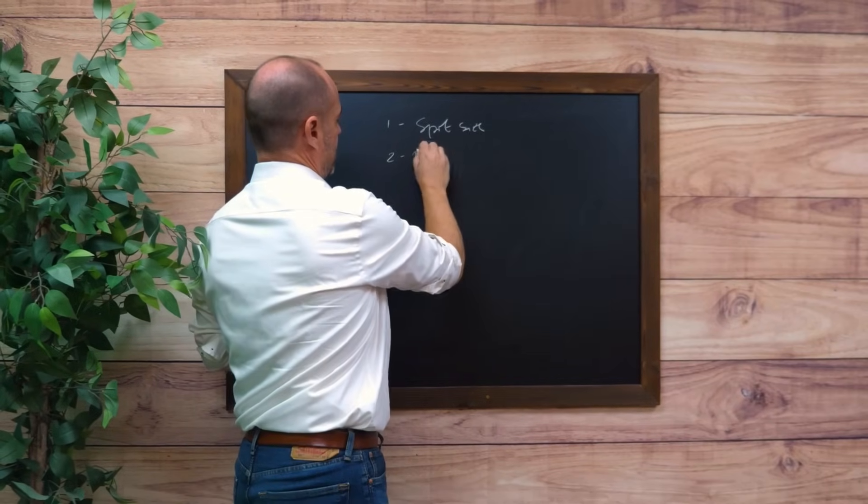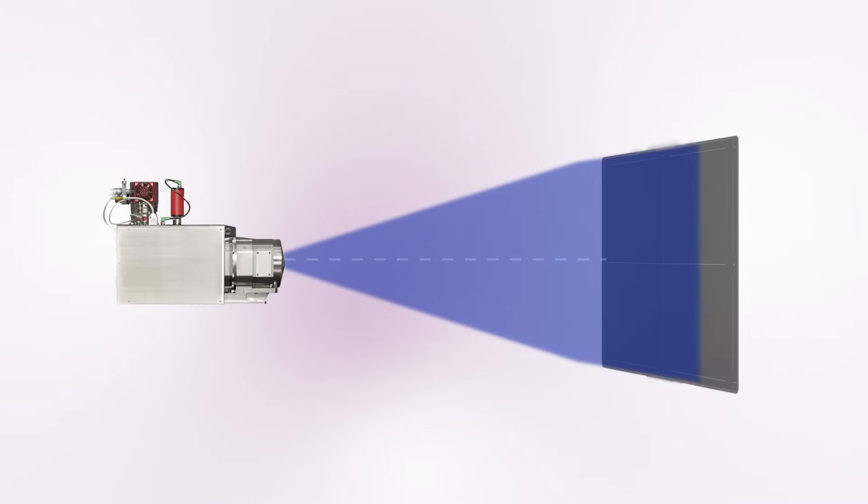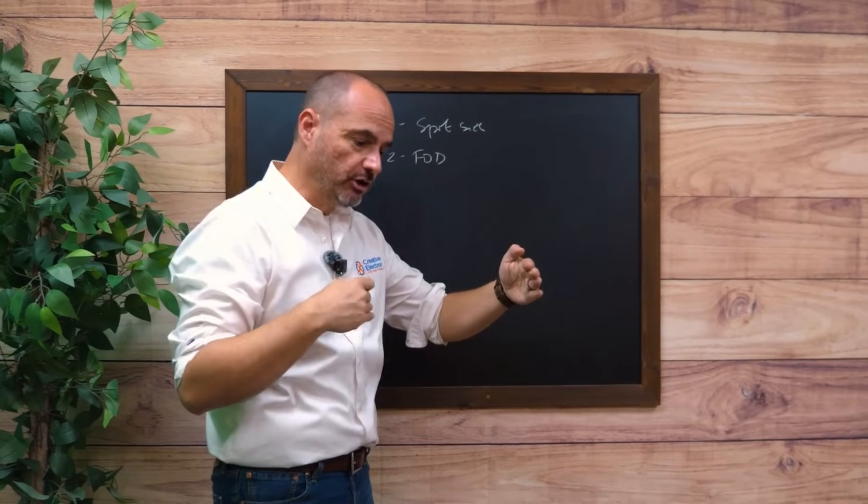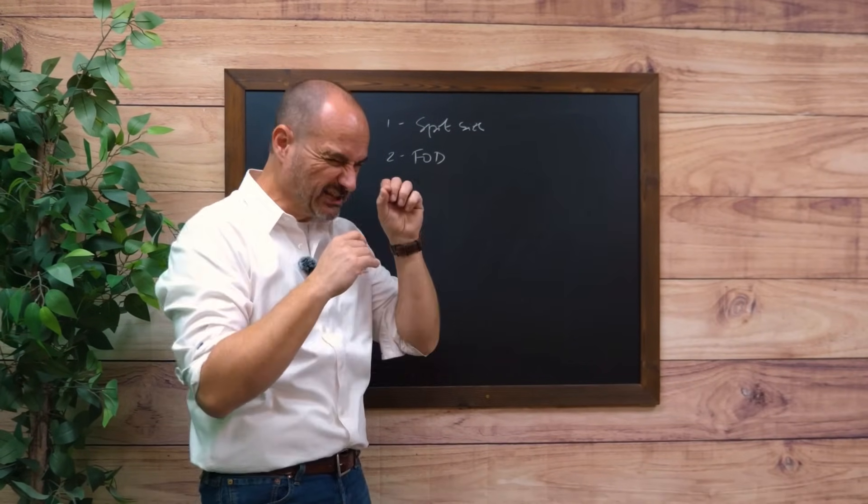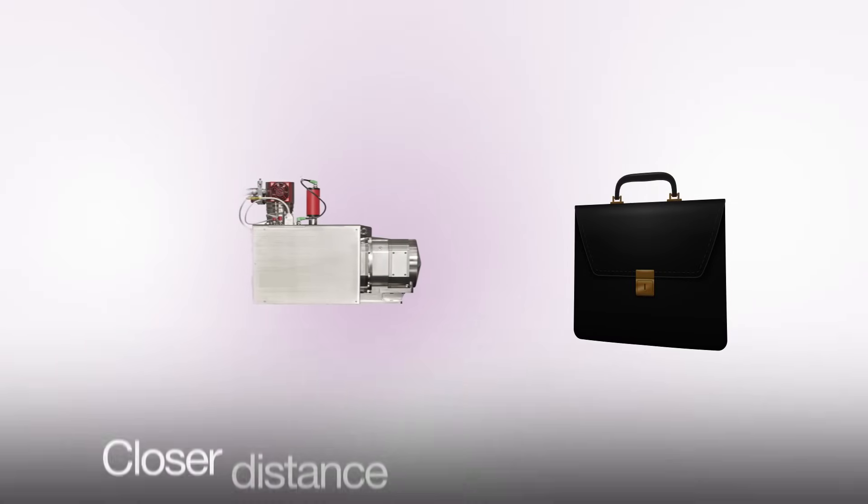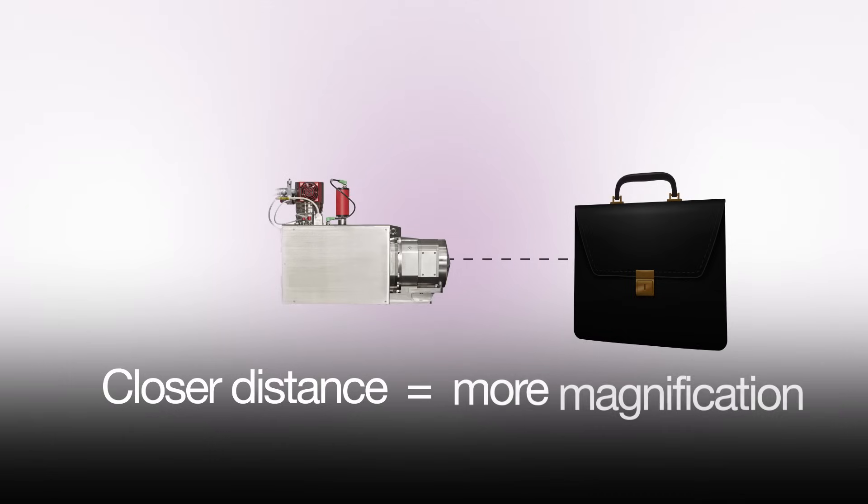The second is FOD, or how far the target of the x-ray source is from the object we're trying to image. The closer you can get the source to the location where the reflection, transmission, and creation of x-ray photons occurs, the more magnification you can achieve.